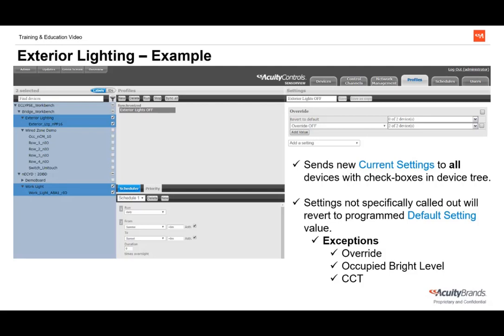Remember that all settings not specifically called out in the profile will revert to their default settings value, except for override, occupied bright level, and correlated color temperature, since changing these settings has immediate effects on the lights. Schedules will show up here, or they can be deleted if the profile is meant to be run from a button press on a scene controller. In our exterior lighting example, we've chosen the profile to start at sunrise and end at sunset, so from sunrise to sunset the selected devices will have their override value changed to off.